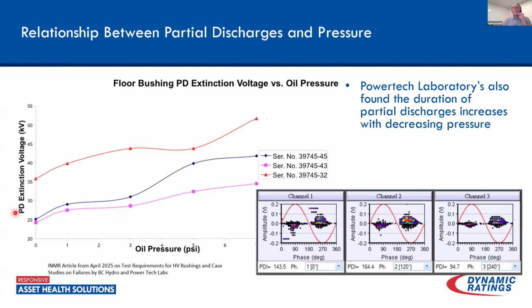The other thing that they noticed is that when we introduce pressure, basically, I already talked about how harmonics can impact when PD starts and when it extinguishes. Oil pressure can do the same thing here. So here we're looking at 7 psi, the top curve. My partial discharge is going to extinguish at 50 kV, meaning that once it starts, it's going to extinguish at some point, in the upper part of that sine wave. Whereas at lower pressures, it's going to continue for a longer duration. So it's going to start sooner and end later. The duration of that partial discharge activity is going to increase, which again is going to increase the insulation degradation, both in our bushings as well as in our transformer.